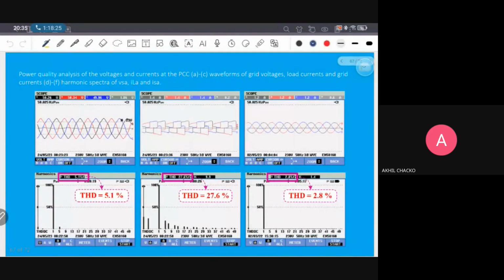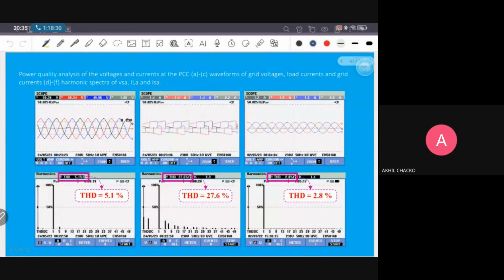And this is the power quality analysis we did with the grid control system. Here this is the grid voltage, this is the load current, and this is the grid current. These diagrams and waveforms are self-explanatory. By observing the grid voltage, you can see there are some harmonics in it, and when we checked with the power quality analyzer, we received 5.1% THD.